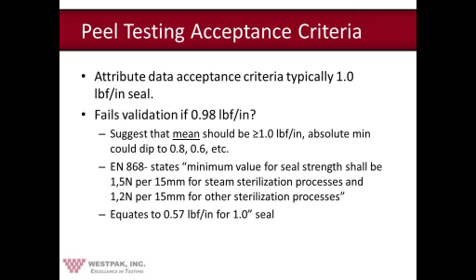Now, we've seen validations fail because one seal measured 0.98 pounds force, and you're talking after a product build, after sterilization, after transit testing, accelerated aging. Once it finally gets through all that, a 1 inch seal hits 0.98 pounds instead of 1 pound, and the whole validation fails. It's a bummer.